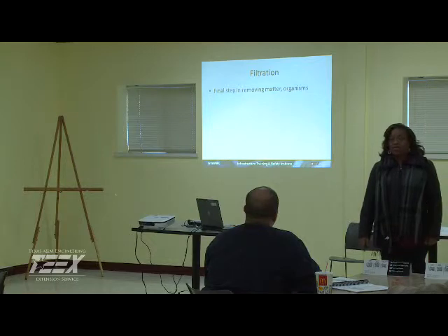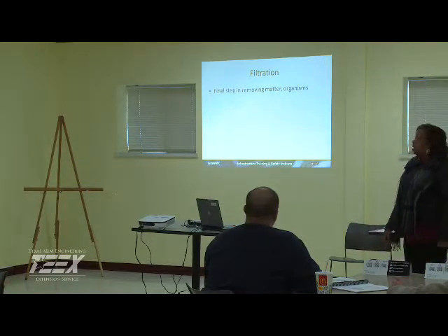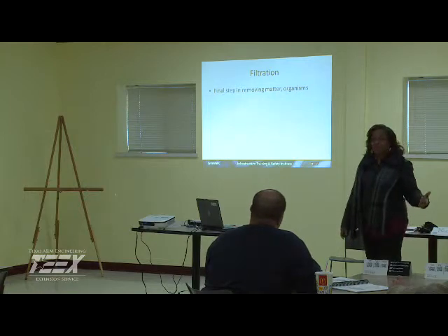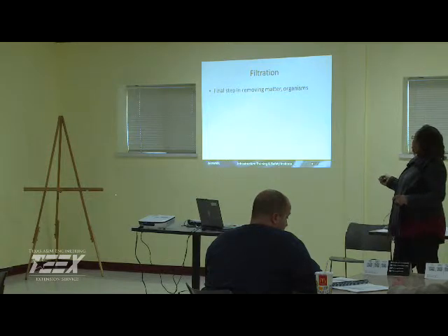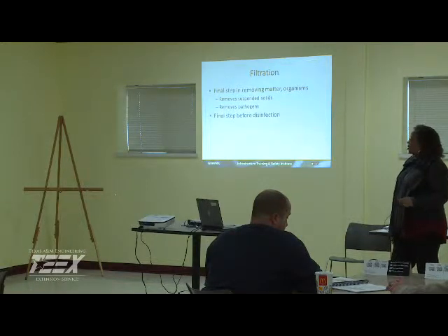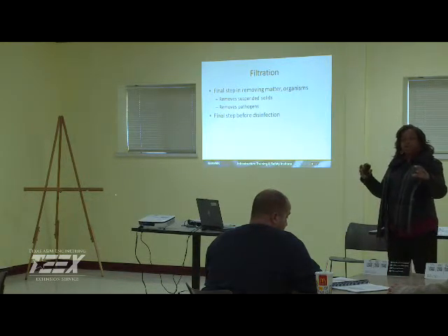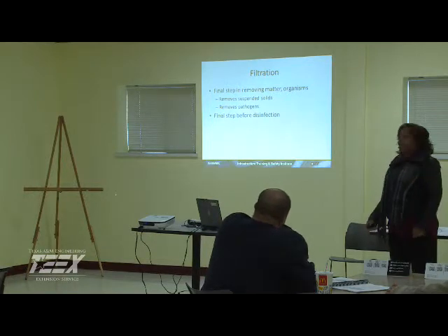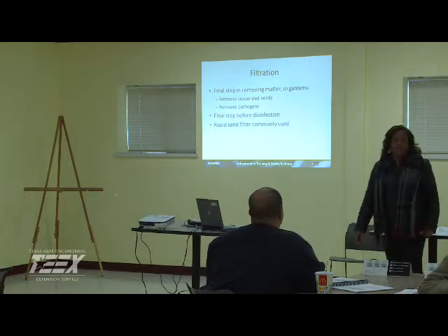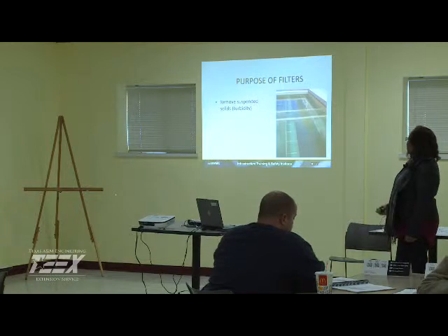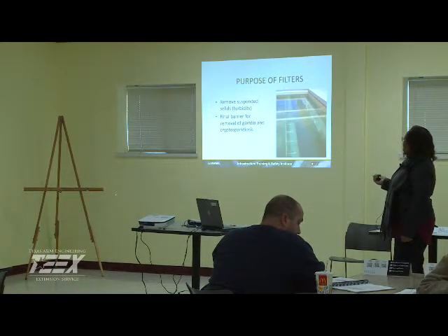The final step to make sure that we remove all the pathogenic organisms, especially those that are resistant to chlorine, will be the filtration process. It is the final step for getting rid of these organisms. It helps to remove suspended solids and pathogens, because sometimes bacteria or protozoa can hide in the turbidity particles. It's the final step before disinfection, and the rapid sand filter is one that is commonly used. With the filters, we're looking at a barrier for removal of Giardia and Cryptosporidium.